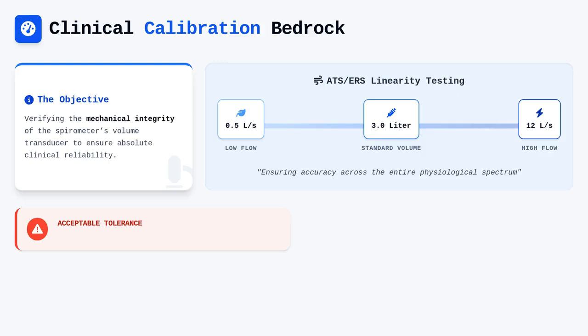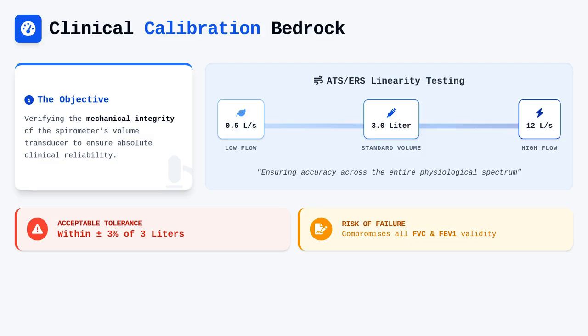You must document every injection, confirming that the measured volume remains within the acceptable tolerance, usually within 3% of the expected 3 liters. Failure to maintain these tolerances compromises the validity of every FVC and FEV1 measurement collected throughout the day.